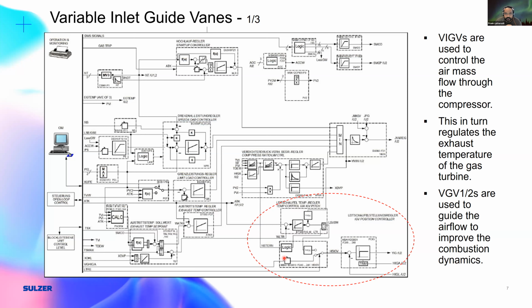So the first stage is typically known as the variable inlet guide vane. Actually, this concept is not too old. The first gas turbines built in 1975, for example, did not have any inlet guide vane. It means during startup, you just had a screen to prevent birds from being sucked into the compressor, and then the air went straight in through, and then you had the combustion process. So it was just the valves that were being used. Now you have, in addition to the first stage variable inlet guide vanes, usually two variable guide vanes, which are controlled in tandem with the IGV. Now, the reason for doing this is you want the air mass flow through your compressor to have a very uniform swirl, so that when you get to the burners and you mix them with the fuel, you have as complete a combustion as possible.